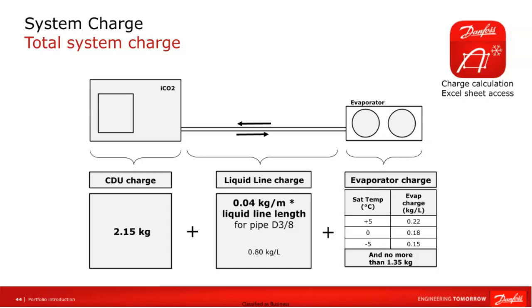The total amount of refrigerant in the system is a sum of the amount of refrigerant in the unit, 2.15 kilogram, the amount in the liquid line, and the amount in the evaporator. The amount of refrigerant in the liquid line is calculated by multiplying 0.04 kilogram per meter by the length of the liquid line in size 3/8 inch.